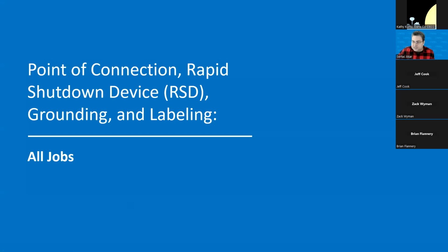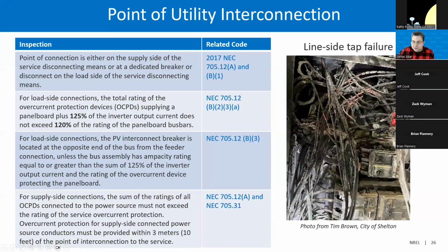After the inverter inspection, the next thing to inspect is the point of connection, which includes the rapid shutdown device, grounding, and labeling of that device. The point of interconnection should be either on the supply side of the service disconnecting means, or at a dedicated breaker or disconnect on the load side of the service disconnecting means. The total rating of the overcurrent protection device, OCPD, supplying a panelboard plus 125% of the inverter output current should not exceed 120% of the rating of the panelboard busbars.